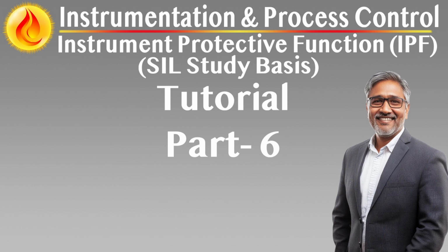Limitations and cautions. Not a substitute for MOC or safety assessment. Automatic MOS should only be applied for well-understood recurring tasks. Unusual or complex override scenarios must still follow formal management of change processes. No overlapping overrides. Systems should prevent activation of multiple overlapping MOS conditions that could compromise functional independence or reduce voting group effectiveness below safe limits.